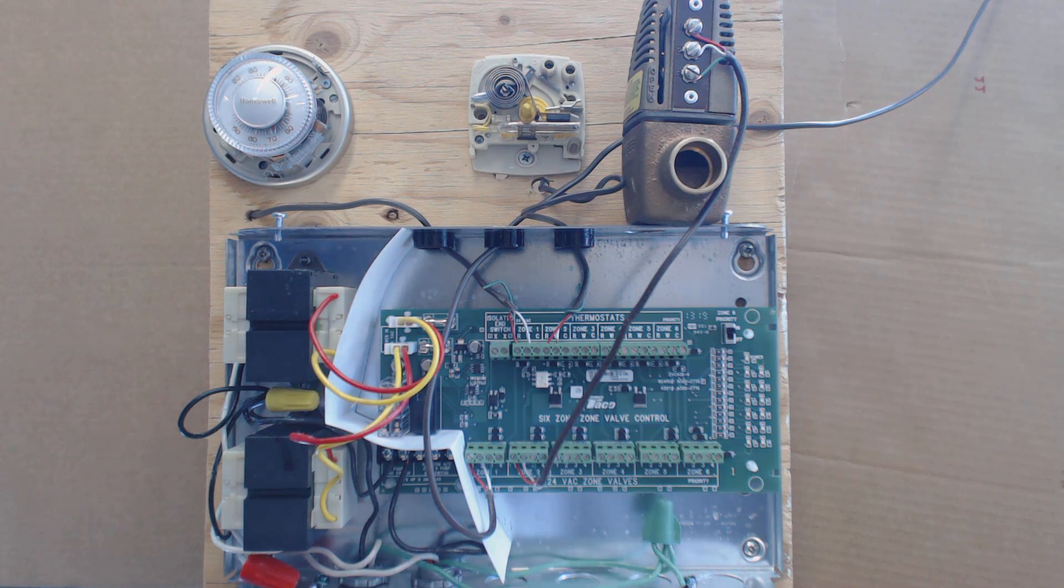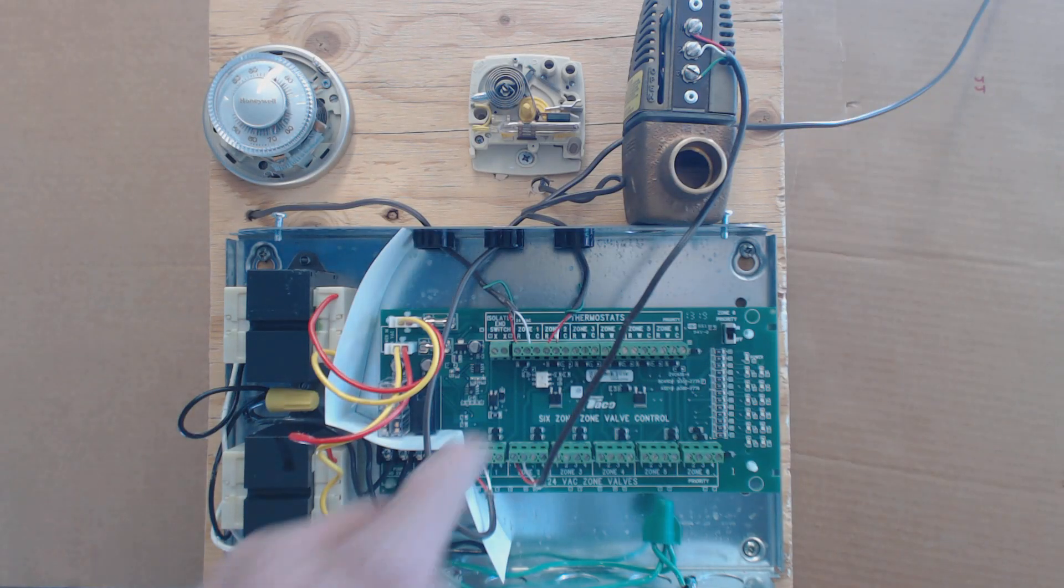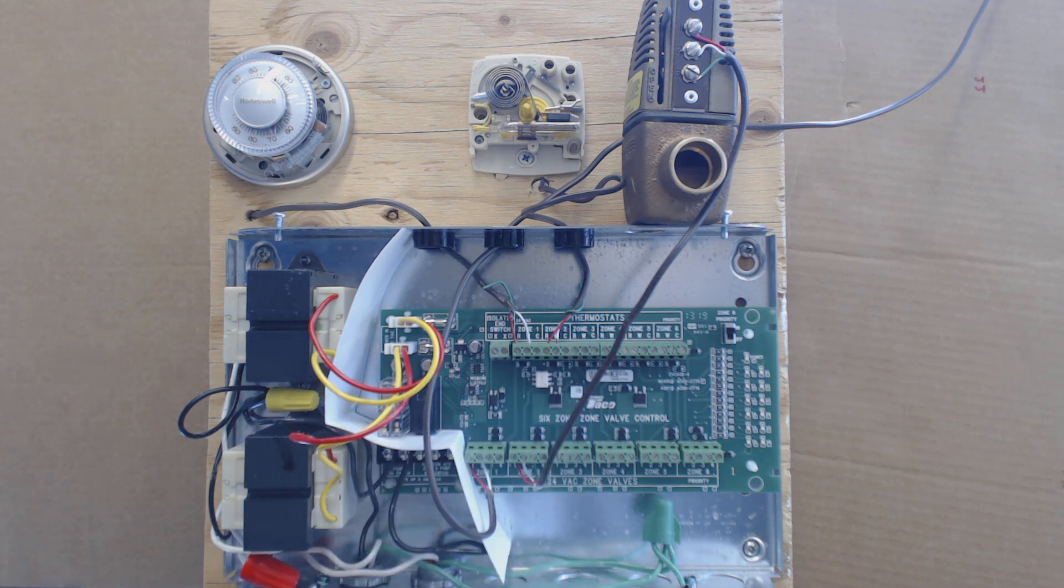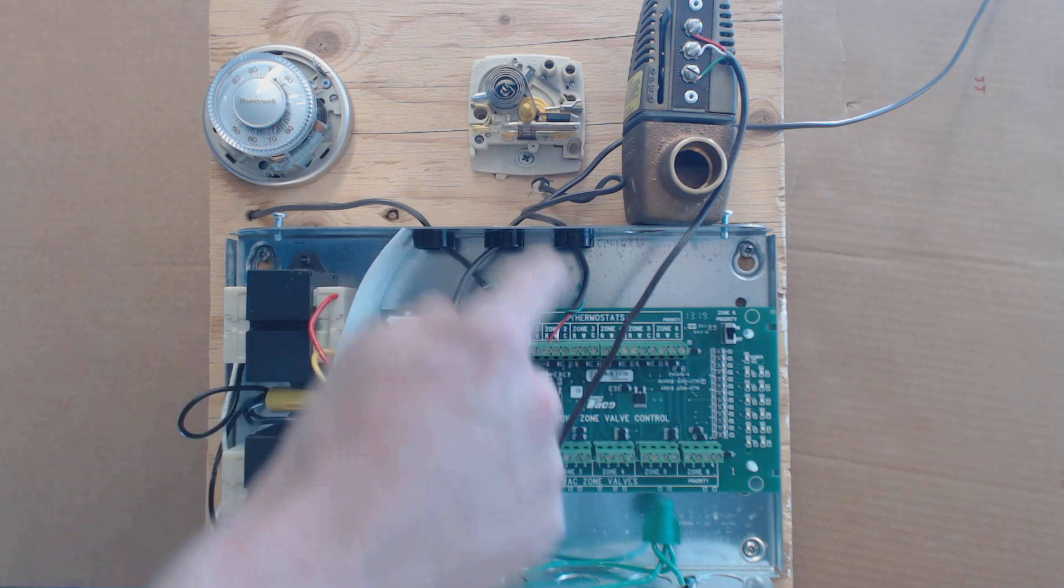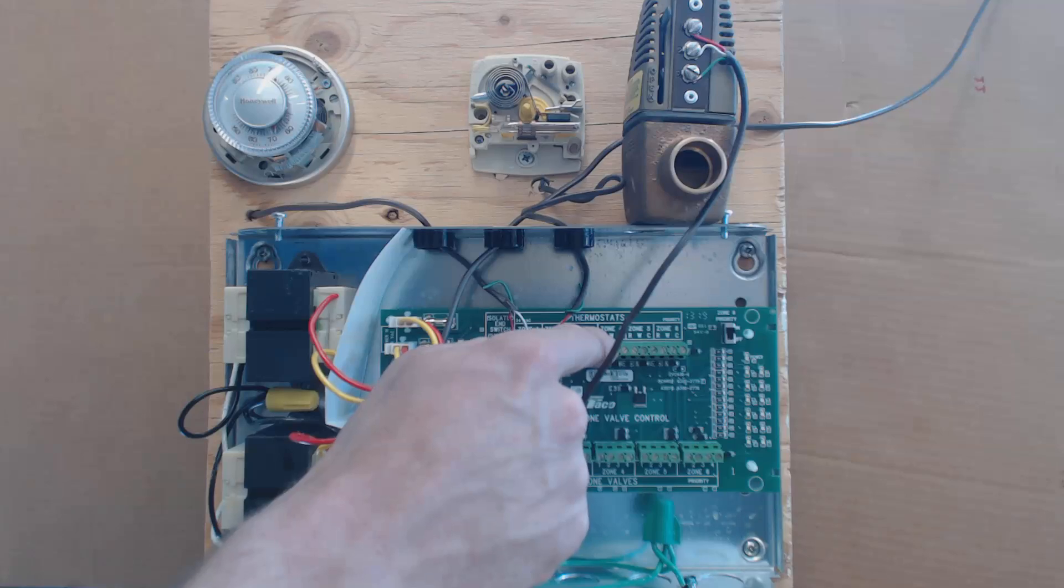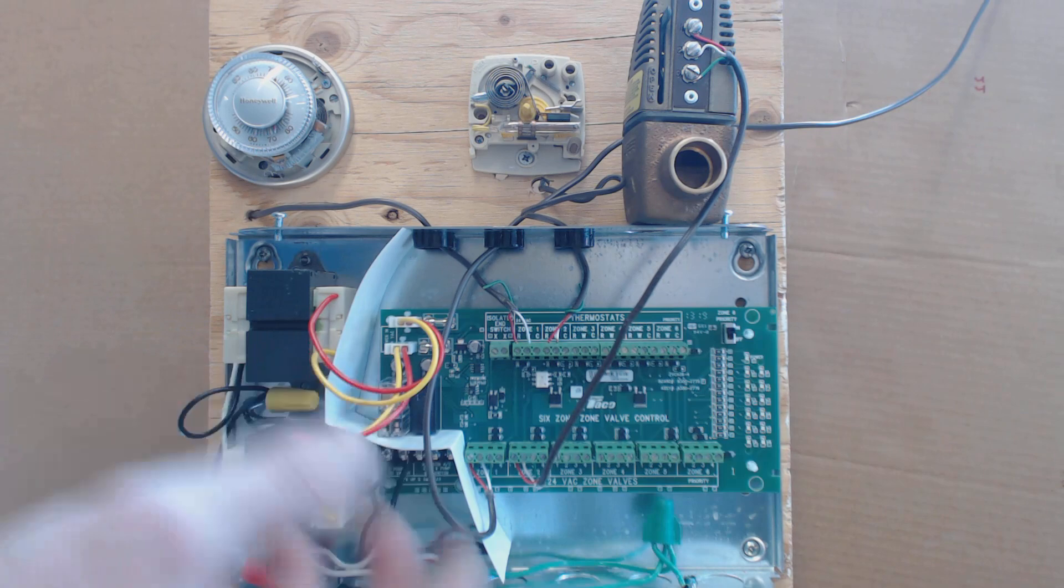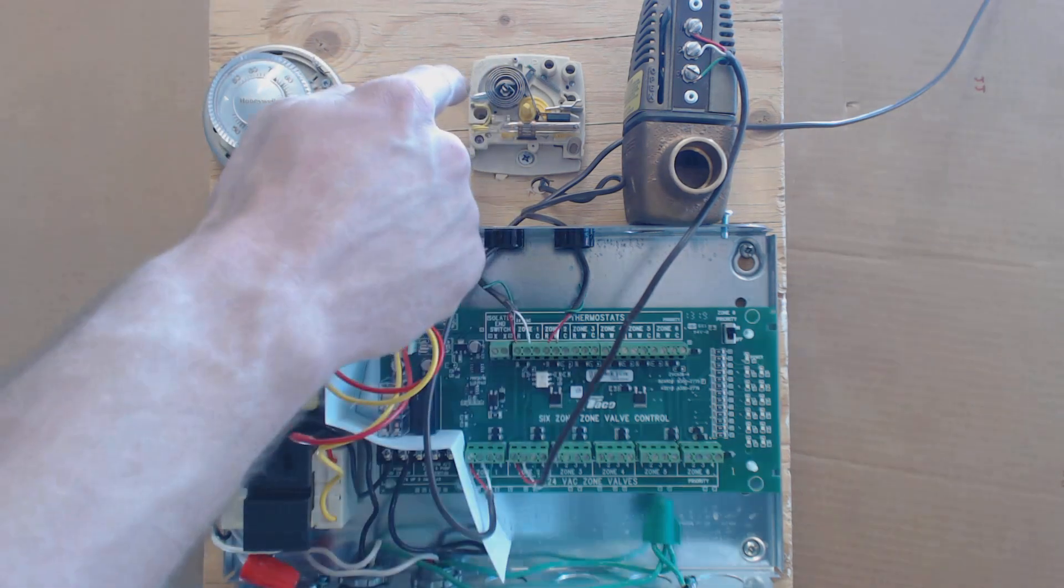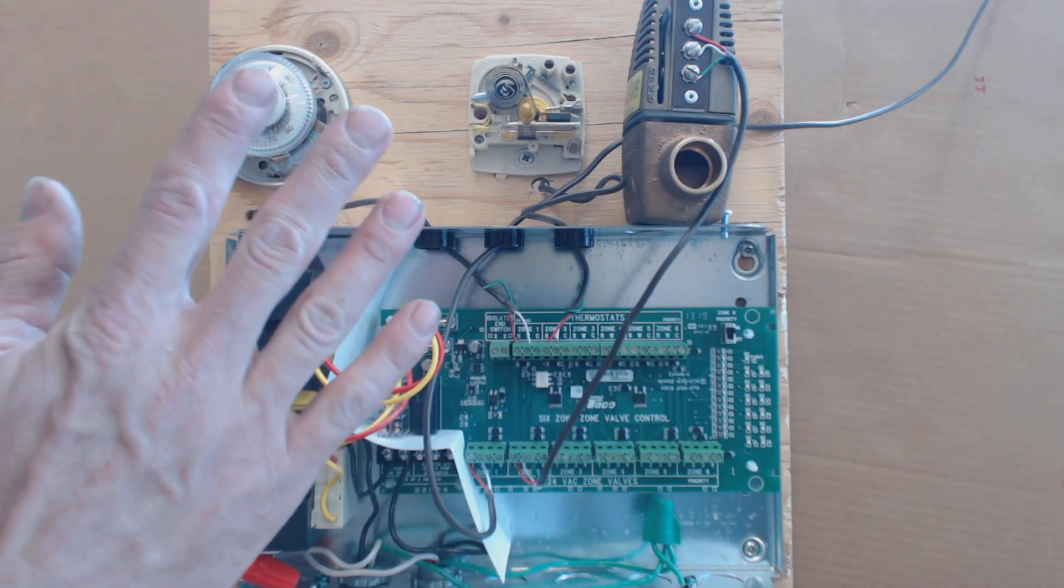So let me just give you the rundown of what's going to happen here. We have on the thermostat zones, let's just take a look at maybe zone three. Zone three, you can see it has R, W, and C. R is the power going to the thermostat, and W is the signal wire back from the thermostat back to the control board. The only time you would use C is if you were to power a digital display. You'd have the power wire coming up to the thermostat, and it would power the thermostat, and then come back down to the C terminal that would power the thermostat.